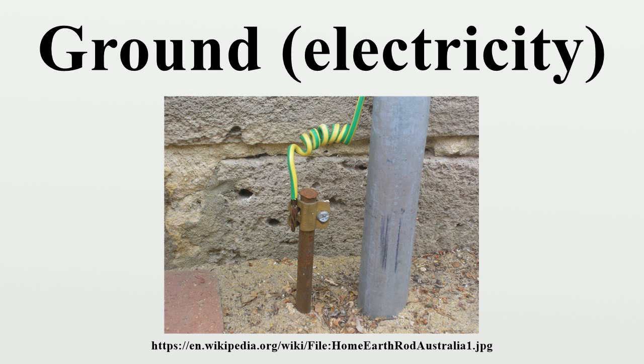Ungrounded systems where the danger of electric shock is high. Special ungrounded power systems may be used to minimize possible leakage current to ground. Examples of such installations include patient care areas in hospitals, where medical equipment is directly connected to a patient and must not permit any power line current to pass into the patient's body.